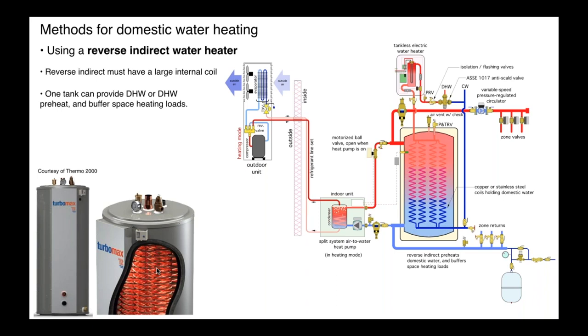So one nice thing about reverse indirect is that one tank can serve as both the buffering for the zone space heating loads and also as either, depending on temperature, it could fully heat domestic hot water or it could be viewed as a preheat with an electric tankless water heater as a final boost. And again, I'm showing the electric tankless water heater. If your requirement for domestic water is 110 degree water, 105 degree water, that's all within the capability of what that heat pump can do. But remember, if you're using outdoor reset control to try to optimize that coefficient of performance based on space heating, the warmer it gets outside, the less preheating you're going to have, and the more that supplemental water heater is going to have to come into play.